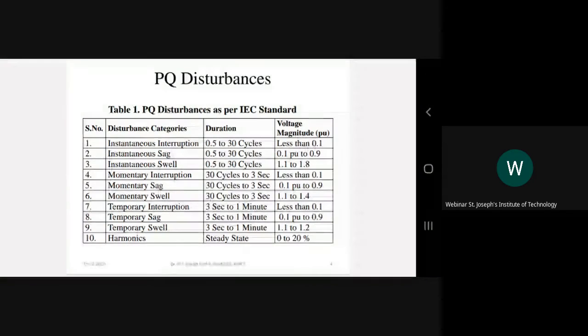Then for momentary cases, the duration increases from the instantaneous, right? From the names themselves we understand instantaneous, momentary, and temporary. For momentary, it is 30 cycles to 3 seconds. 3 seconds means how long? 150 cycles. So 30 cycles to 150 cycles, the problem exists in the power system network. The problem is under the category of momentary. Again, it has three classifications: momentary interruption, momentary sag, and momentary swell. The interruption is less than 0.1 per unit, sag is 0.1 per unit to 0.9 per unit, and swell is 1.1 per unit to 1.4 per unit.